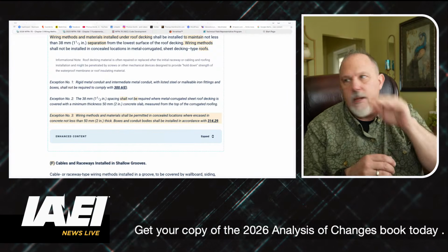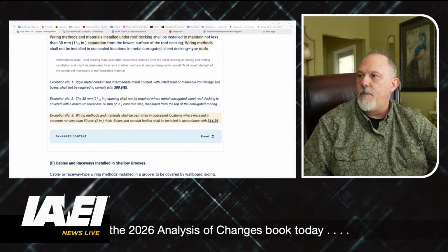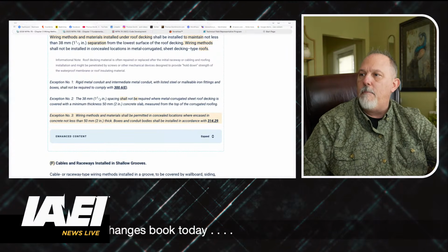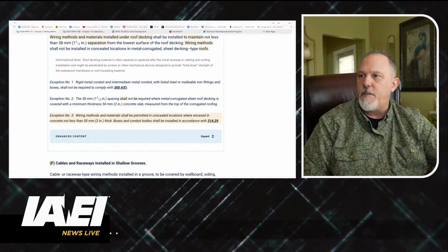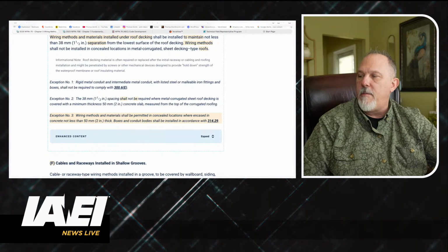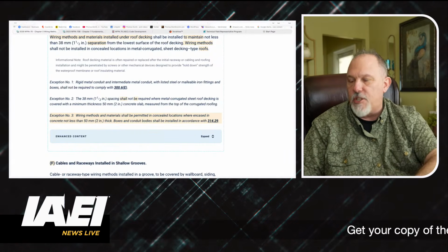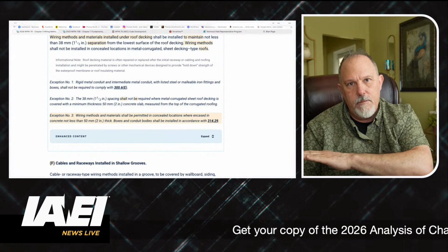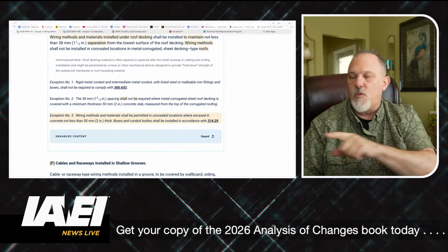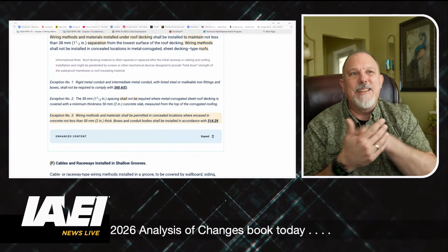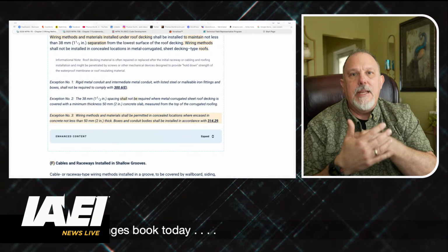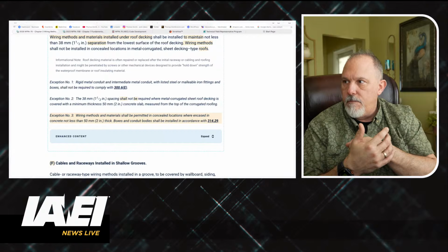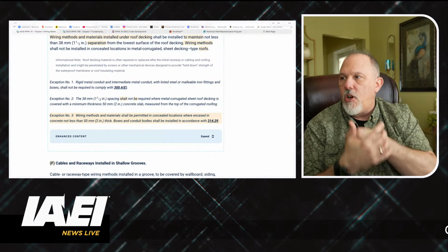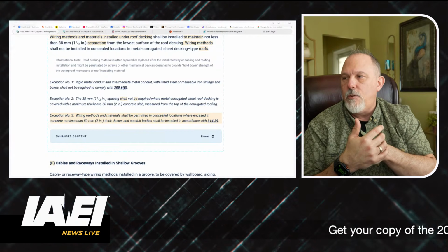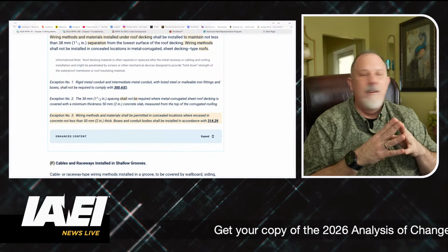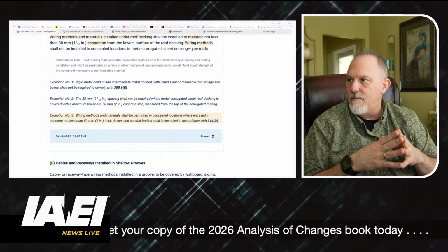Okay, so that's if I'm putting the raceway. Exception number 2 says where metal corrugated sheet roof decking is covered with a minimum thickness. Well, that's previous language, so that exception was already there. The new exception is when the raceway itself is encased in concrete not less than 2 inches thick.